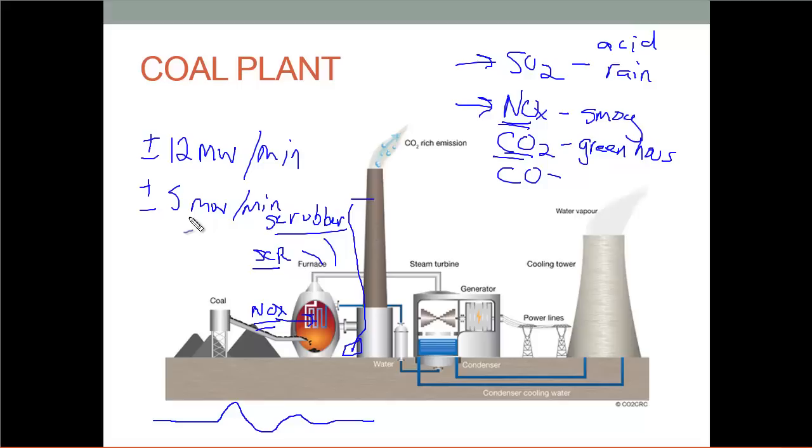So again, when your renewable generation goes up or down, the only thing you can do is to operate this power plant and swing the unit, and increase the amount of fuel. And it takes a little while. You increase the fuel and you put more heat in here and you generate more steam. And then after a couple minutes, you start generating more electricity. There's a delay. And also after you take a little heat out of here, maybe you put a little less fuel in there, but it takes a little bit for that heat to dissipate and then for your generation to go back down. So you're kind of limited in what you can do going up and down.